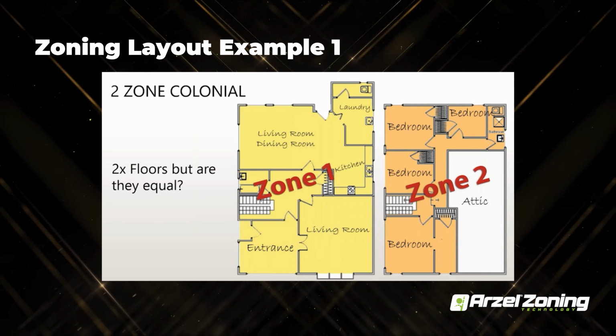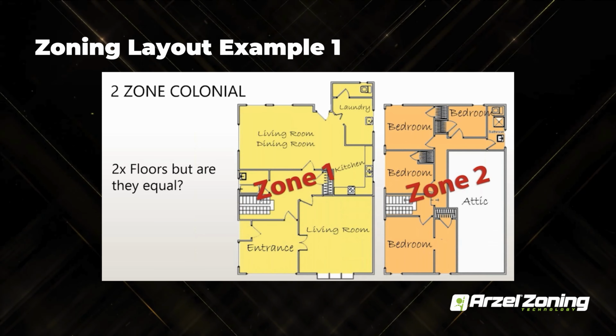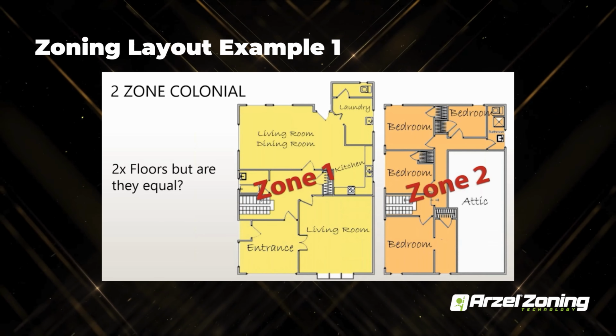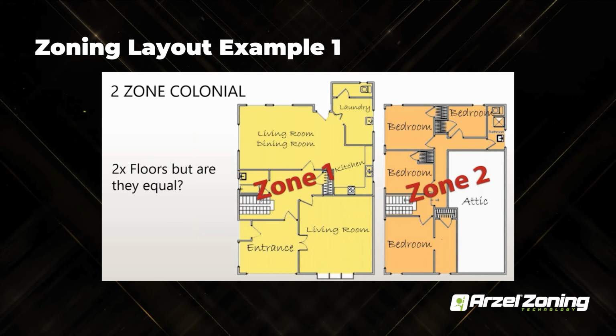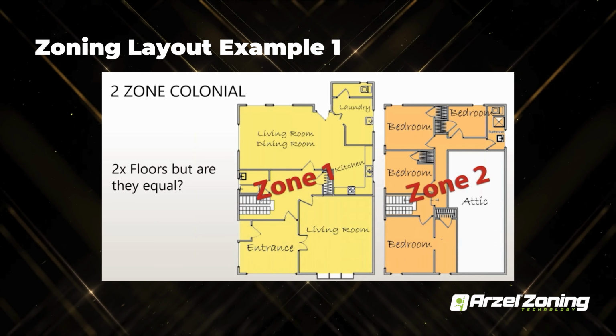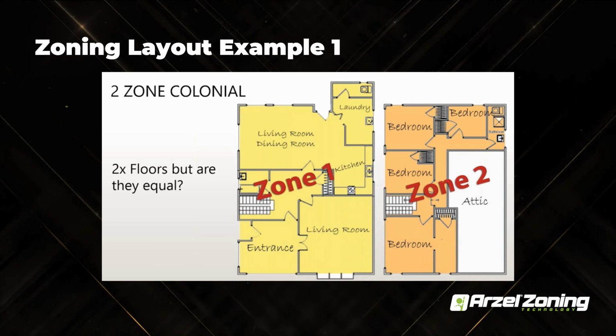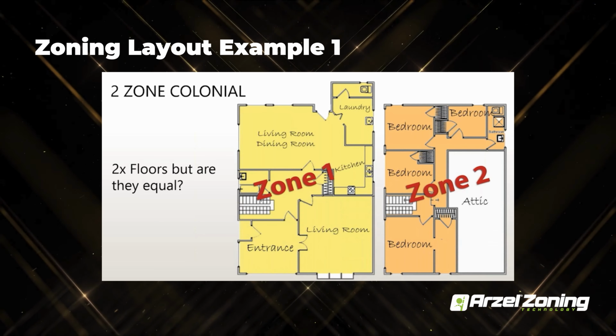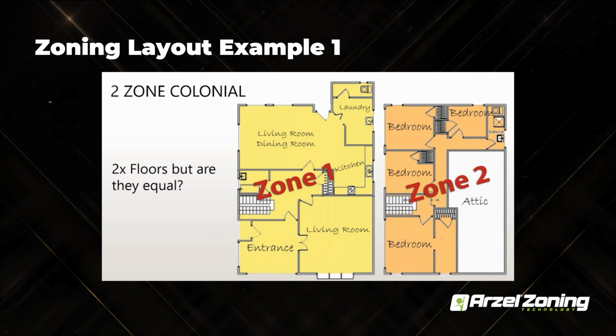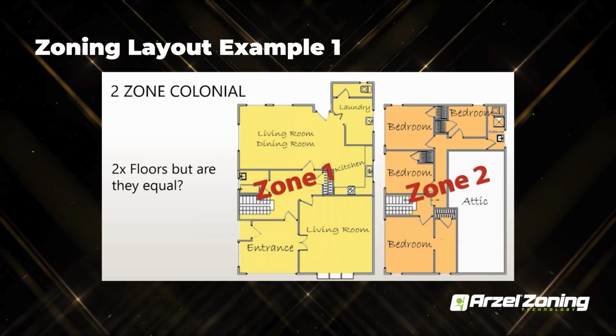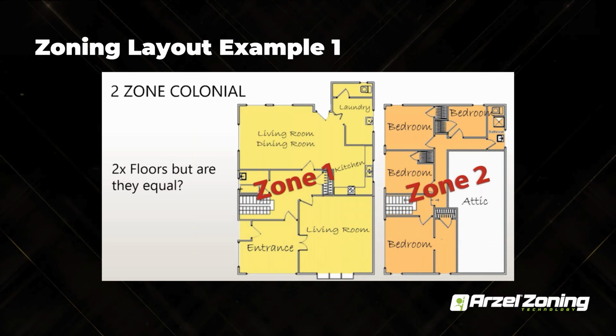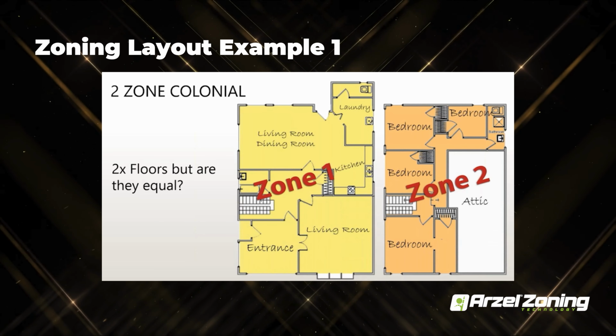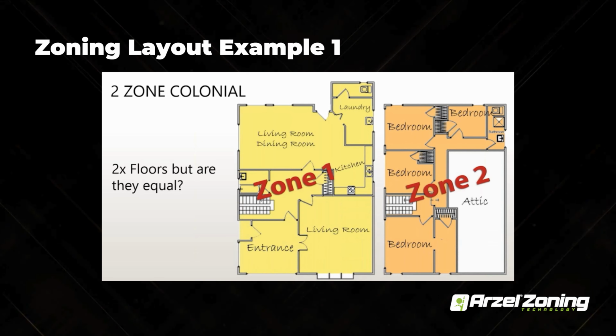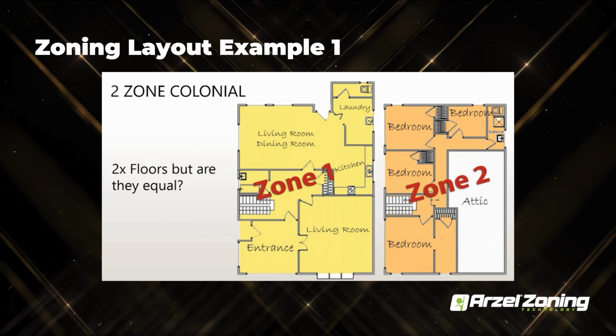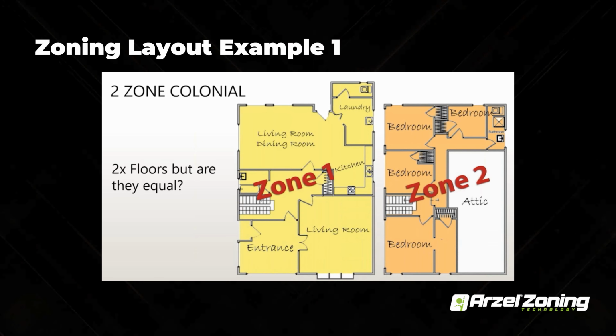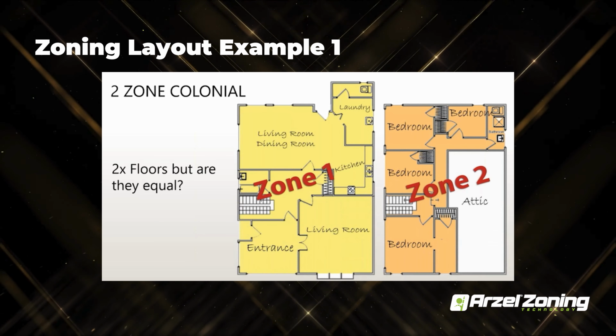When you're looking at your jobs out there, these are just a couple examples of your typical homes. This is going to be your typical 2-story house, so you've got a zone 1 and zone 2. One of the things to consider when you are splitting up zones is you want to do a load calculation on both zones to make sure that they're somewhat equal if you're splitting into a 50-50 split like that. You also want to take a look at how many CFM outputs, so see if you have the same amount of CFMs or not. This will help you better determine what size bypass you're going to need, or if you're going to need a bypass at all. If you can, the best thing to do is utilize that zone weighting feature and try to minimize the size of the bypass or get rid of the bypass completely. That's really what we strive for, and that's what we're going to be touching on in this presentation.